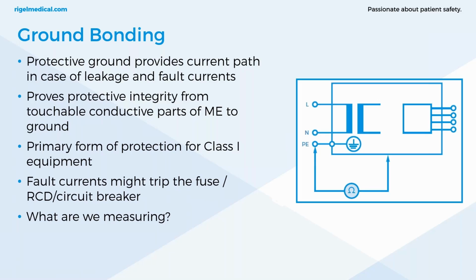Now, over time, connections or bonds within the unit can fail due to high workload, high stress medical environments, and these poor contacts and any film resistance that builds up between those contacts can be imperceptible to a visual check. So we need to double check that these ground bond values are still within the specified limit. Fault current, so we also want to ensure that the values are correct.